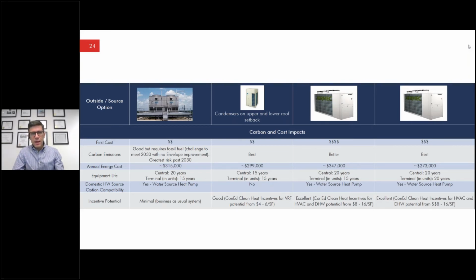Important question, I want to touch on that. I don't have a specific COP answer for that right now, but if you look at the annual energy cost comparison of these four options, the VRF and the air source heat pump, the second and fourth on this list, have a slightly lower utility cost than the first alternative. That suggests those operating COPs were annually better from a utility cost standpoint. The selections there have COPs at around the 5-degree outdoor air condition in the range of 1.6 to 1.7, but annually, as it gets warmer out, on a 25-degree day they're operating at a higher COP, and those utility cost numbers take that into account over the course of the year. So it's not a single COP number, but annually these heat pump solutions are seeing more attractive results.